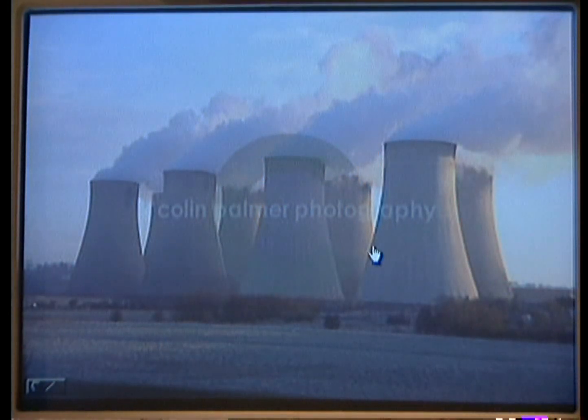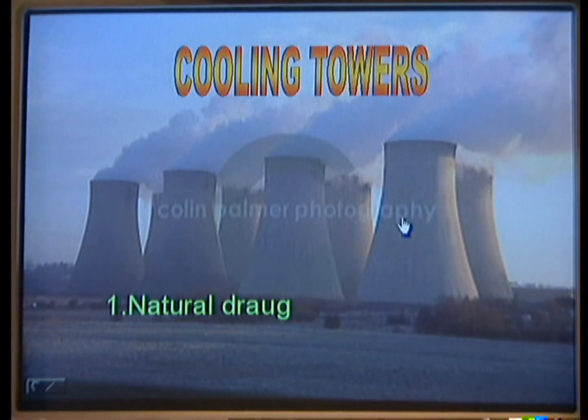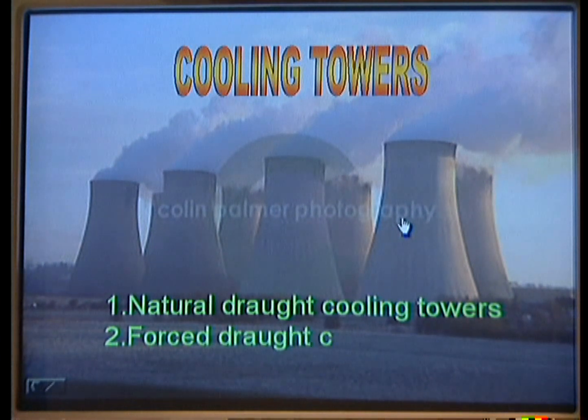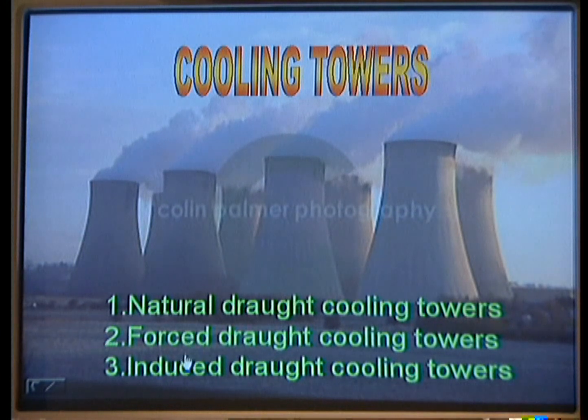Let us go to the cooling towers. Yes, this is the cooling tower. Cooling towers are generally made with concrete, wood or steel. Depending upon the requirement, it is semi-enclosed. Depending on the shape, cooling towers are classified into natural air draught cooling towers, forced draught cooling towers and induced draught cooling towers. If you are using an external fan, then it is a forced or induced draught cooling tower. If you are not using any fan, that is a natural draught.